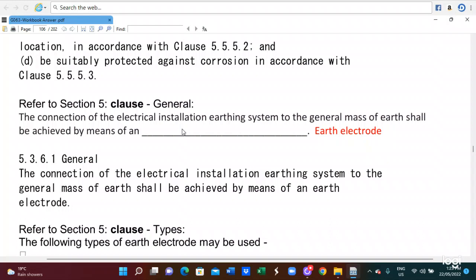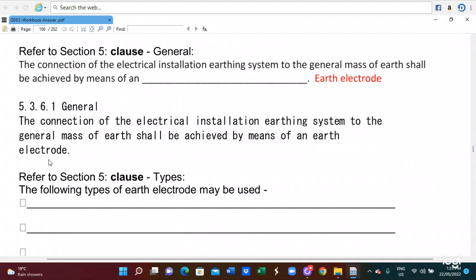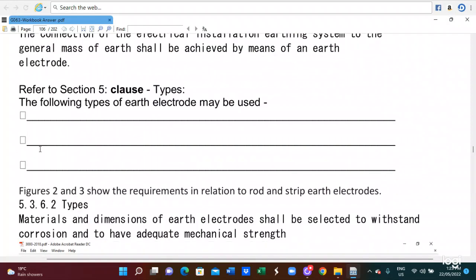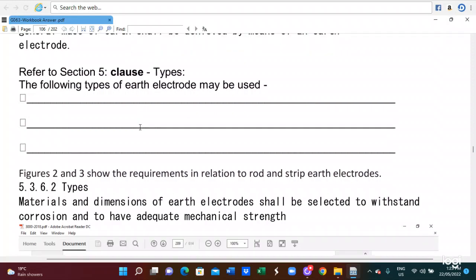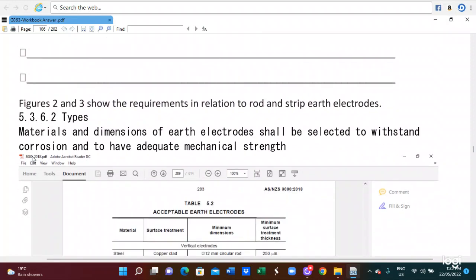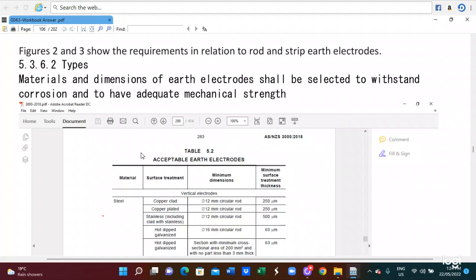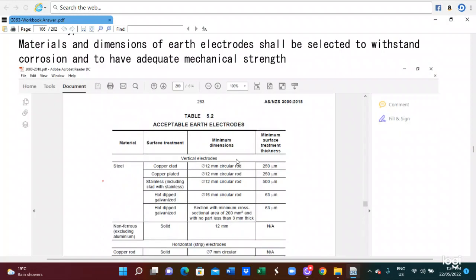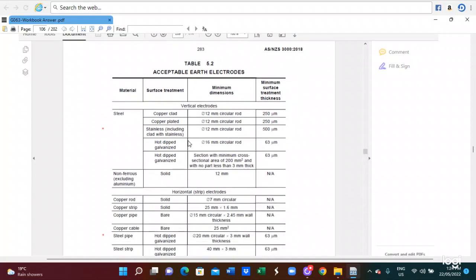And also the general clauses: the connection of the electrical earthing system to the general mass of the earth shall be achieved by means of the electrode. In this case, you refer to 5.3.6.1. The connection of the electrical installation earthing system to the general mass of the earth shall be achieved by means of the electrode. So in this case, you have to refer to section 5. The reference is clause 5.3.6.2, acceptable earth electrodes. You can see there is a material and a diameter for the electrode. You can get it from Table 5.2.